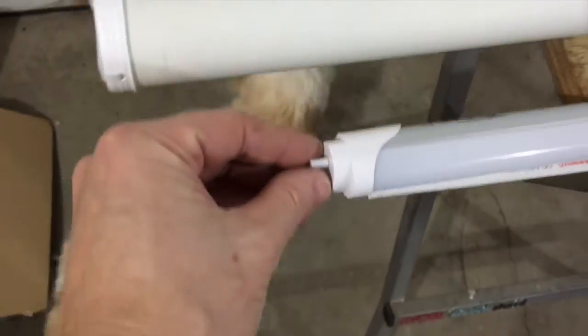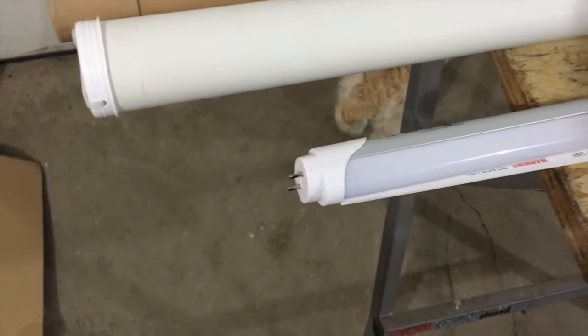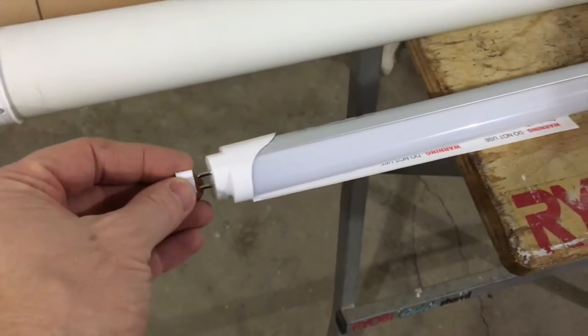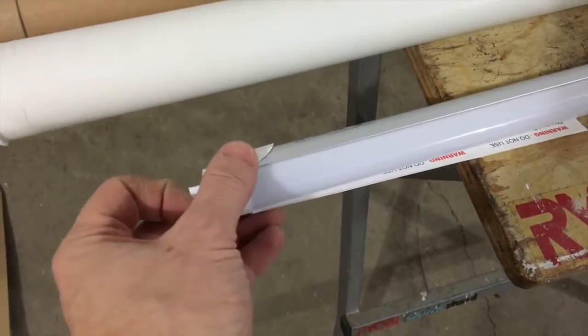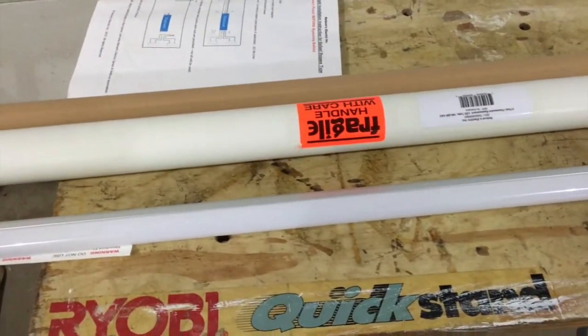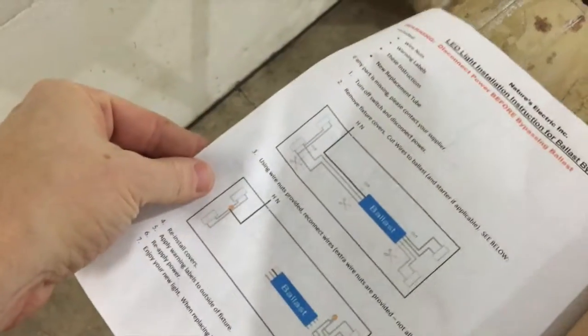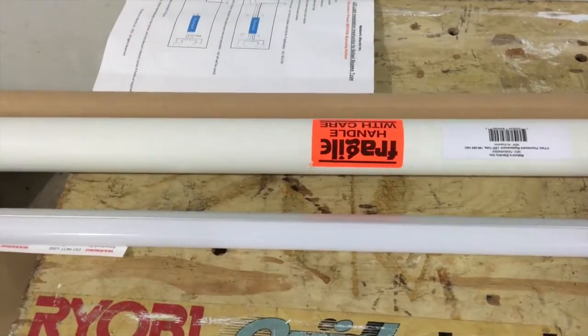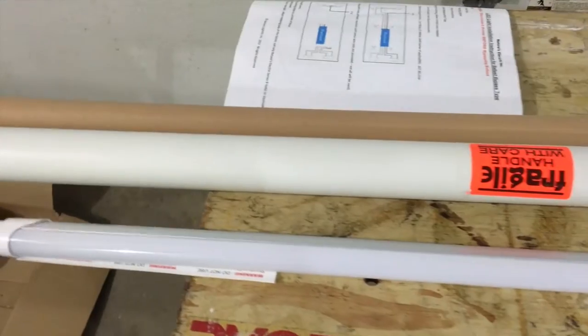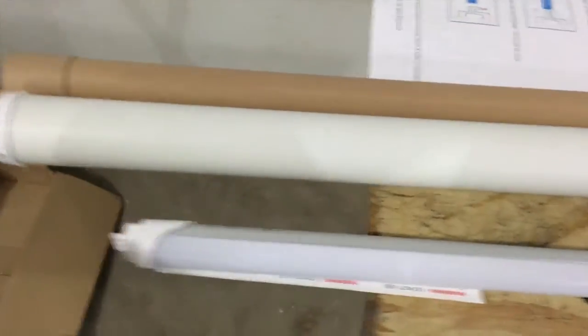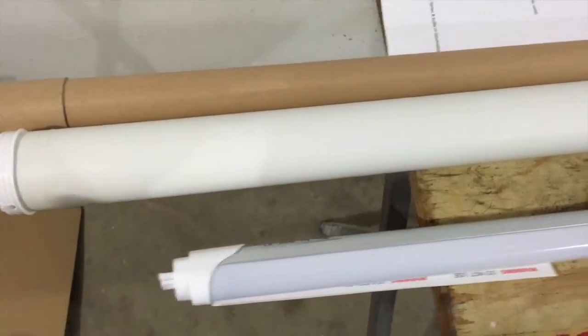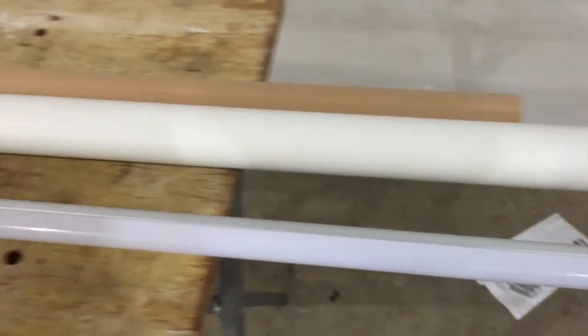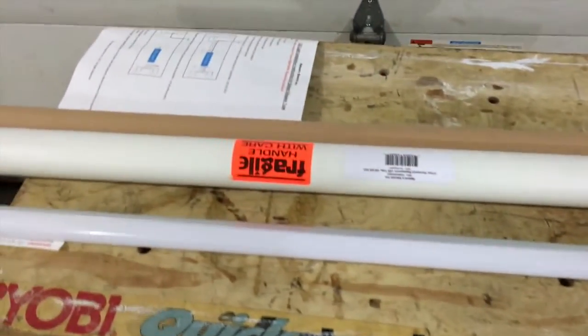The light is a replacement for your current four-foot tube. Now what I liked about this one is that I had to rewire, and I have the instructions here, everything you need to do the rewiring. Basically with this system, you're taking out the ballast. You're going to run the hot to one end and the neutral to the other end, and that way you've got your light bulb ready to go.